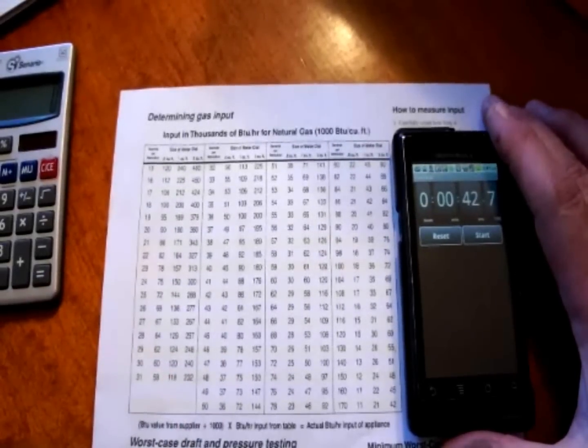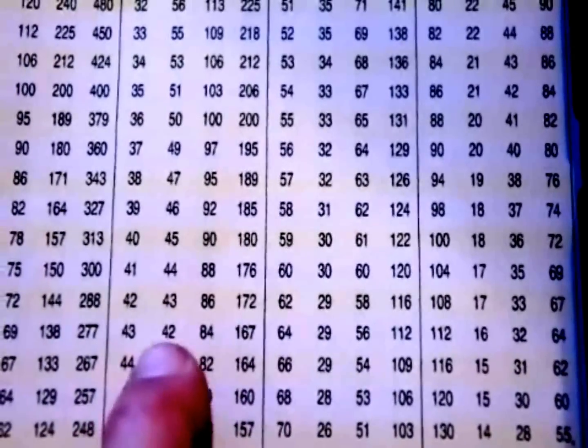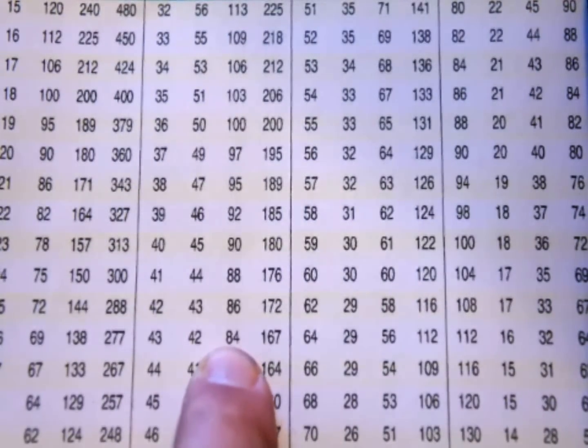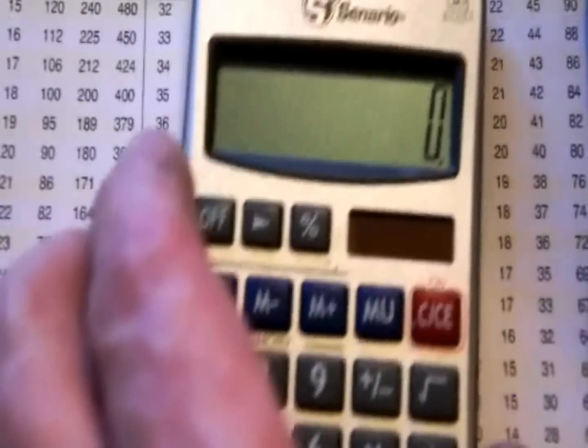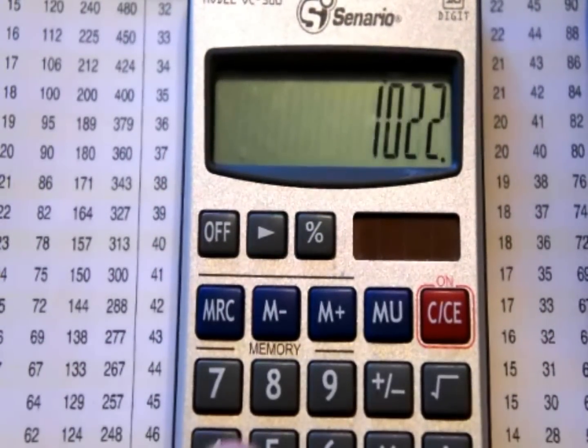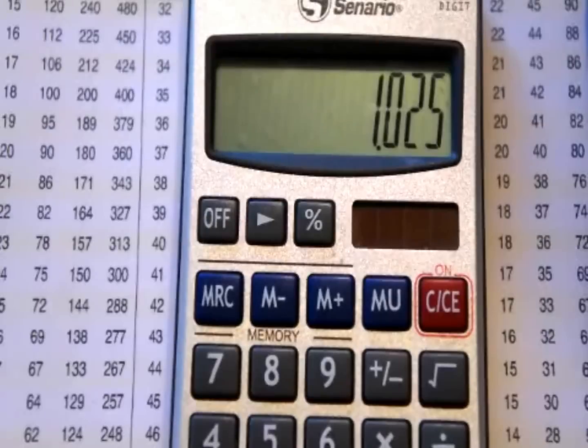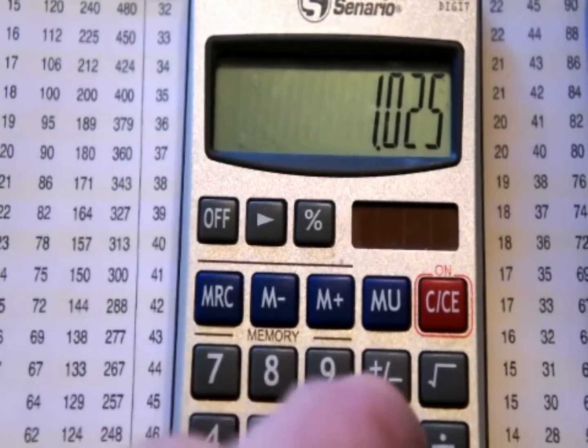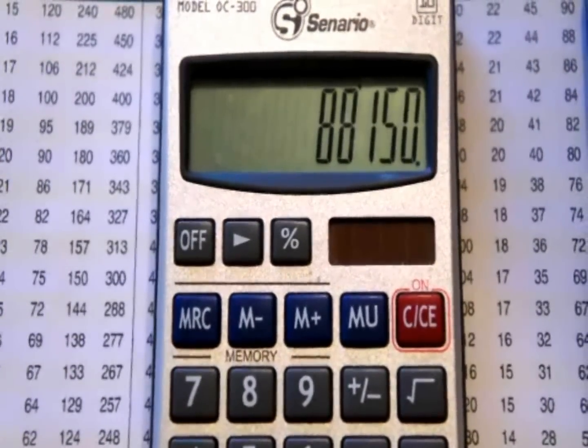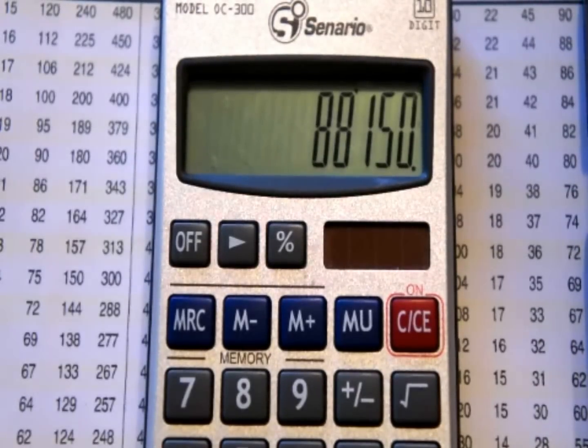Back inside with the gas chart. At 43 seconds on the one cubic foot dial, we're at 86,000 BTUs. Now we do the math: gas input from supplier is 1,025 divided by 1,000 equals 1.025, times 86,000 equals 88,150. So we're still a bit under fire at this point. Let's see if we can get the rest of it out by tweaking up the gas pressure.